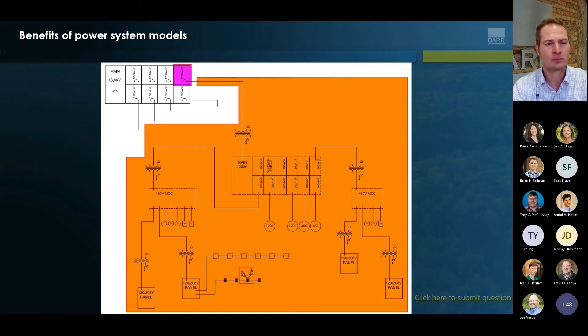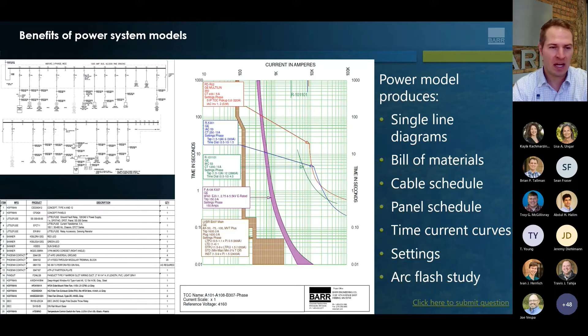So the power model is used for coordinating the power system so the trips occur at the proper level. The power model produces time current curves such as you see here. And then it's also used in developing single line diagrams. The model can actually output a start of your single line diagrams. There's an example of one seen there. The power model also will give you bills of materials, cable schedule, panel schedules, all the design deliverables that are used for procurement and construction.